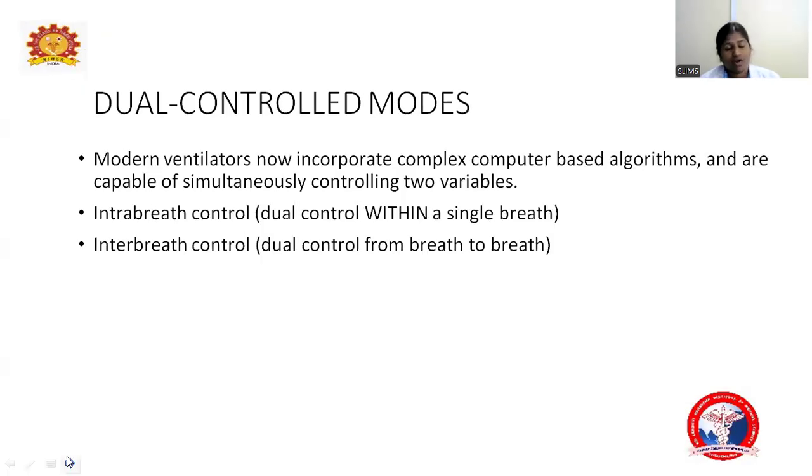So what are the options that are available for us? There are dual control modes, where modern ventilators incorporate complex computer based algorithms capable of simultaneously controlling two variables. But in basic modes, we have only one variable controlled, either pressure or volume. In newer modes, dual control is also there, so we can control two variables in a single setting.